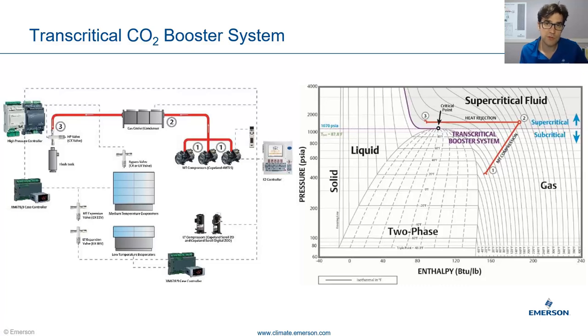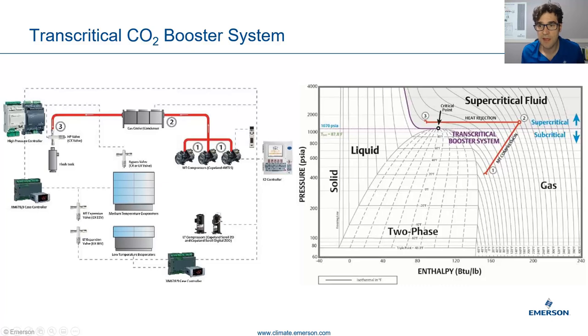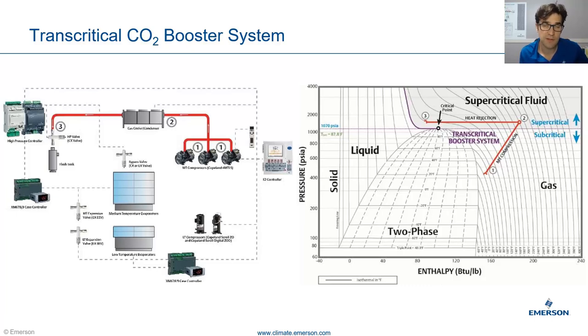We have these high-pressure valves which reduce the pressure from this high — like 1,000, 1,100, 1,500 PSI — all the way down to 500 PSI. That valve is like a metering device, but it has other functions as well. When we're in a subcritical zone, say the high side only goes up to 900 PSI, we go across for the heat of rejection and get into the two-phase zone — we're in subcritical and now we can start to condense. That valve is then monitoring subcooling, maintaining maybe three to five degrees subcooling for that system. The other function for this high-pressure valve is in the middle of winter: it acts like a holdback valve to fill up the condenser so it can continue the mass flow.